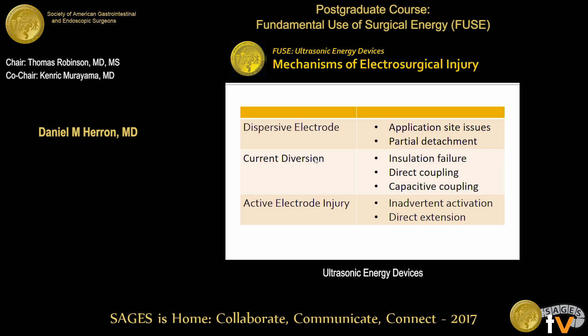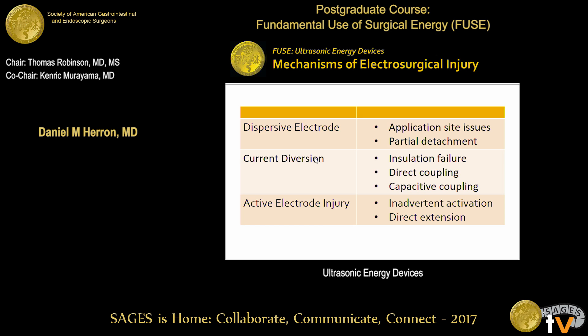We've heard about some of the ways that you can get injury from electrical energy. You can have the dispersive electrode partially pull off the patient's thigh, and that can cause an injury there. You can get current diversion. You can get injury from the active electrode if it touches the wrong thing. These are things you can avoid if you're not using electricity inside the patient.